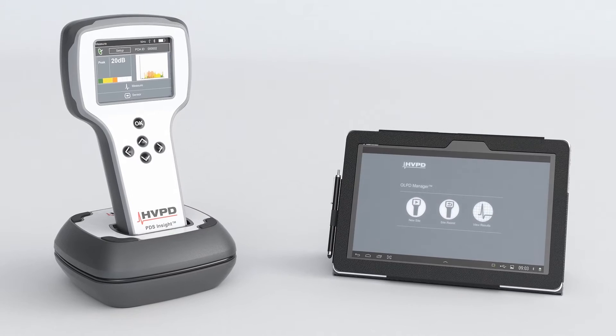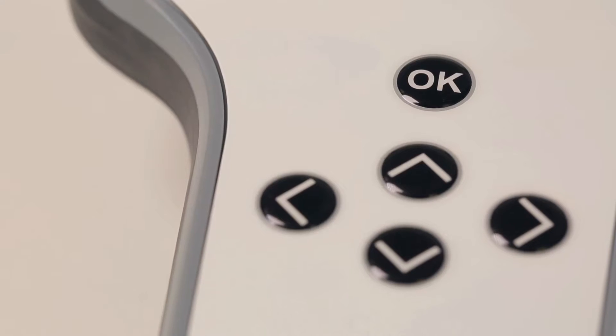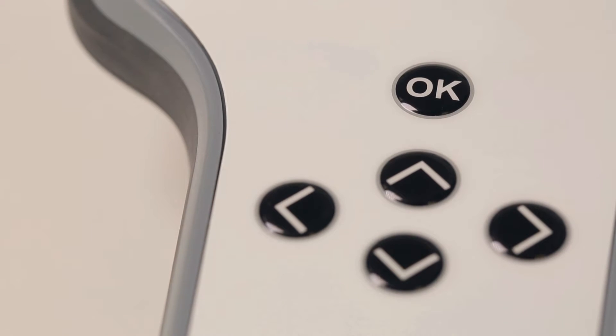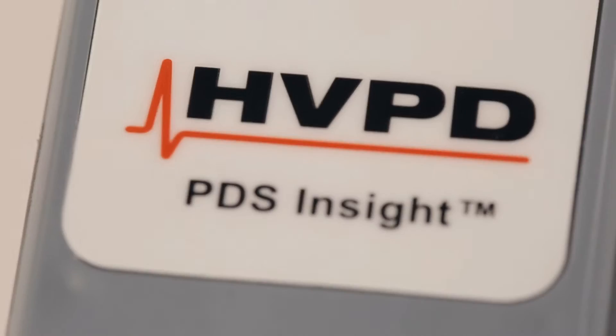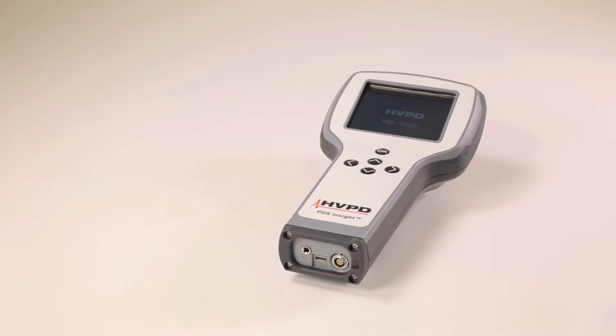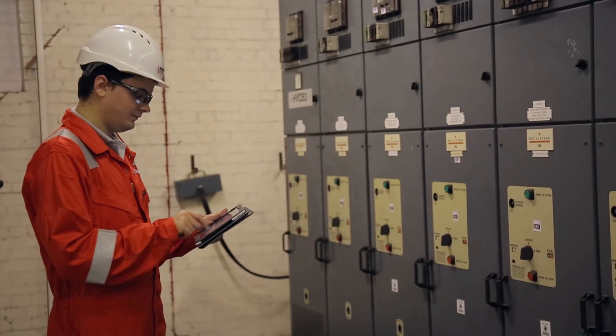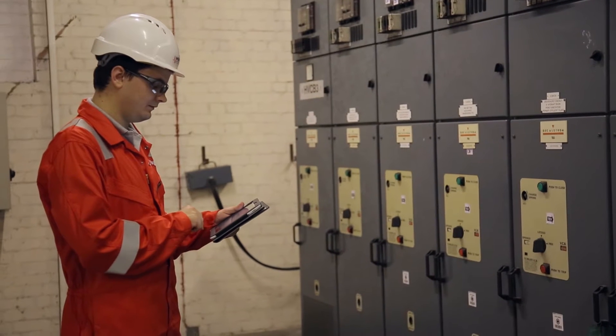Launched in September 2014, the PDS Insight is the world's first handheld online partial discharge test unit supplied with an asset management app for Android, the OLPD Manager. This unit will test power cables, switchgear and other metal-clad plant for the detection of partial discharge activity. Test results are stored on board and can be synchronised with the OLPD Manager app for analysis and trending.